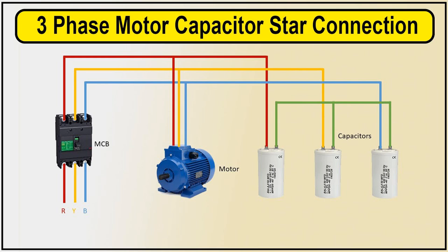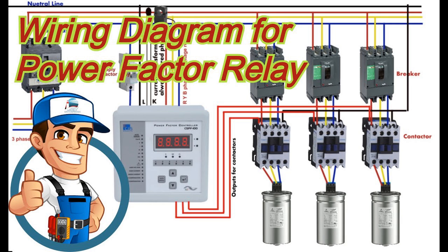The primary function of fixed capacitors is to improve power factor by offsetting the inductive component of the load. By introducing capacitive reactance into the system, fixed capacitors help balance the reactive power and improve the overall power factor closer to unity, 1.0.